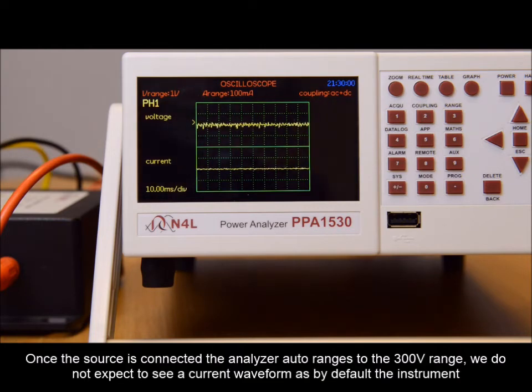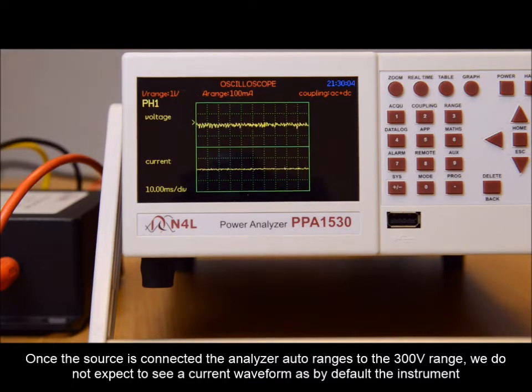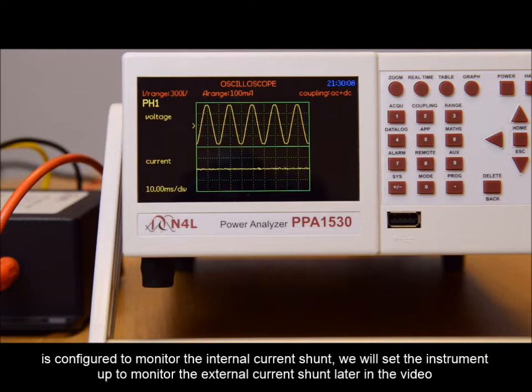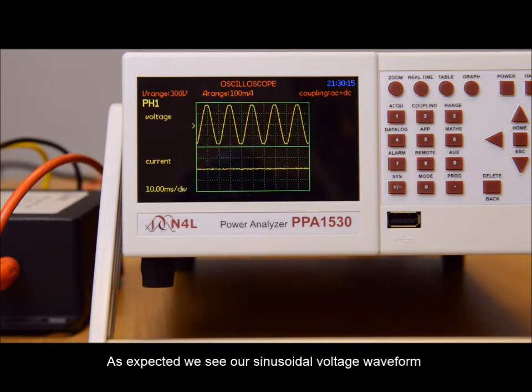Once the source is connected, the analyzer auto-ranges to a 300 volt range. We do not expect to see a current waveform, as by default the instrument is configured to monitor the internal current shunt. We will set the instrument up to monitor the external shunt later in the video. As expected, we see our sinusoidal voltage waveform.